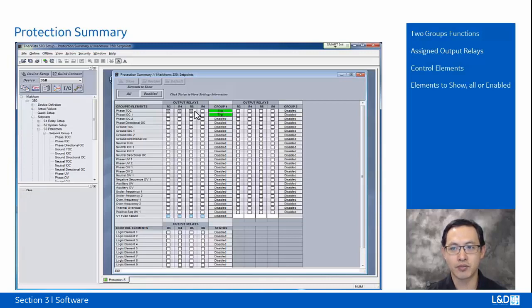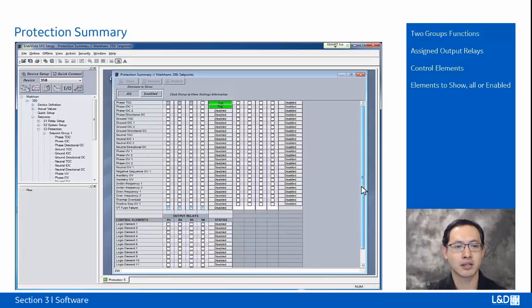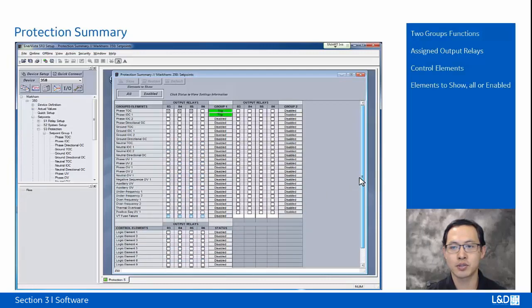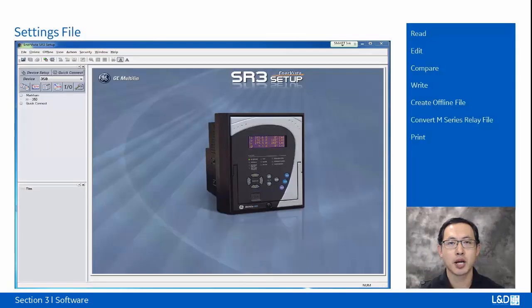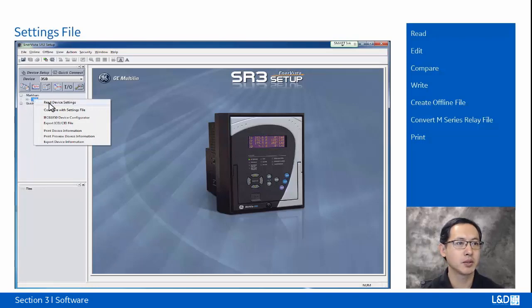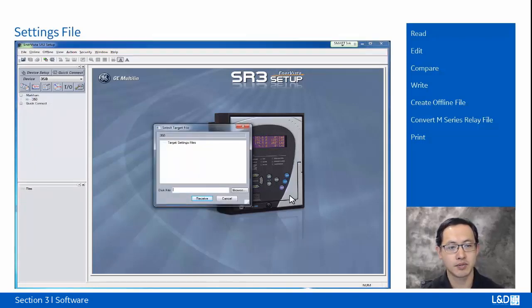We can see the two groups of the protection elements and also the assigned output relays. We can see the control elements and maintenance functions, and we can select elements to be displayed or only enabled. To download a setting file from the online portion to the offline portion, we need to right-click the device name and choose read device settings, and then we can give this device a name, 350, and click receive.